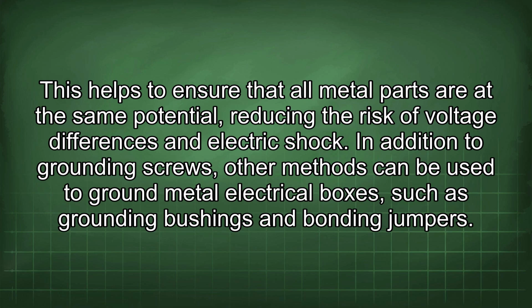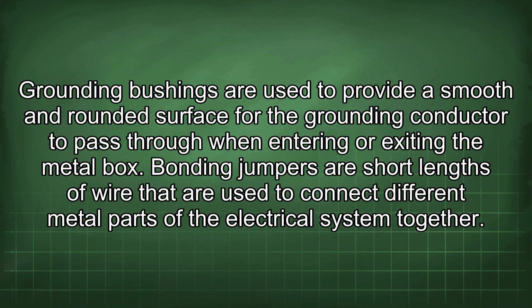and electric shock. In addition to grounding screws, other methods can be used to ground metal electrical boxes, such as grounding bushings and bonding jumpers. Grounding bushings are used to provide a smooth and rounded surface for the grounding conductor to pass through when entering or exiting the metal box. Bonding jumpers are short lengths of wire that are used to connect different metal parts of the electrical system together.